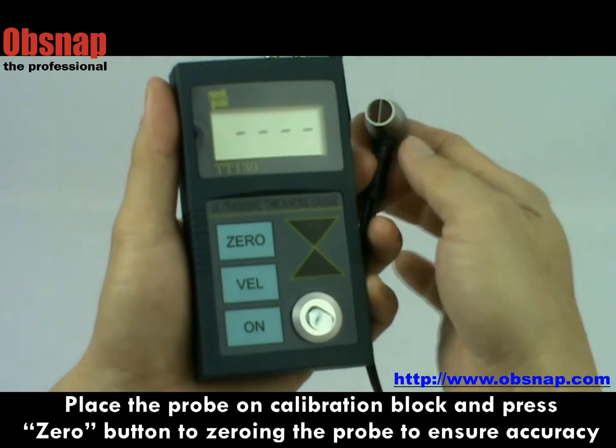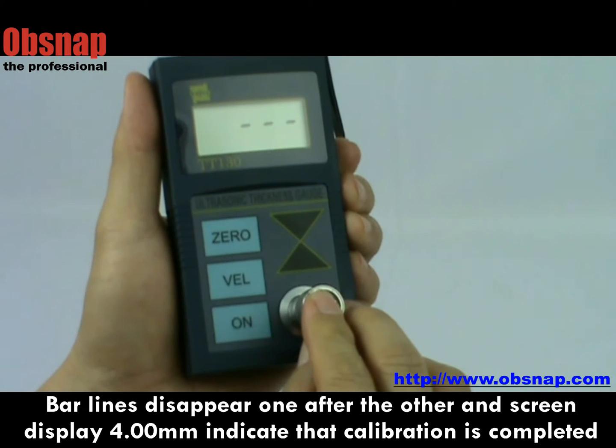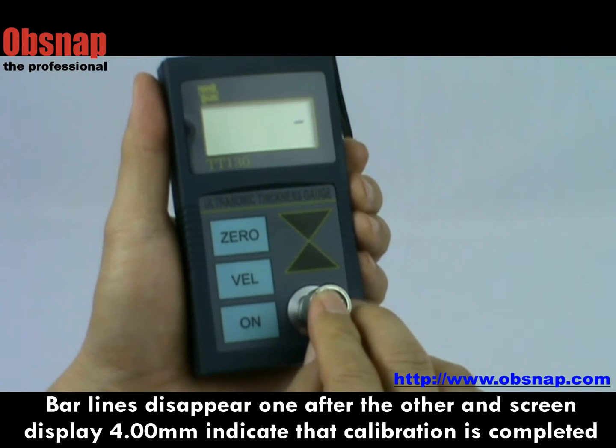Place the probe on the calibration block and press the zero button for zeroing. Bar lines disappear one after another. The screen displays 4mm to indicate that calibration is completed.